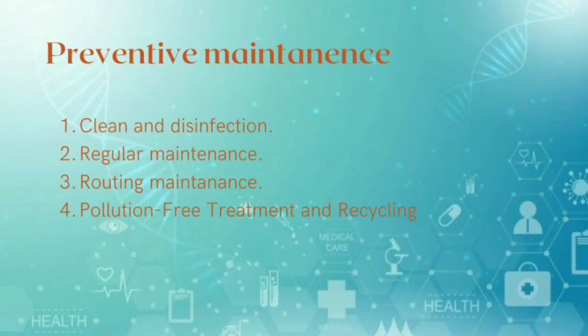Now, let's see what are the preventive maintenance we have to consider. First one is cleaning and disinfection. The machine needs to be cleaned frequently, especially the areas which can be seriously polluted. The pump needs to be turned off from AC power supply before cleaning.